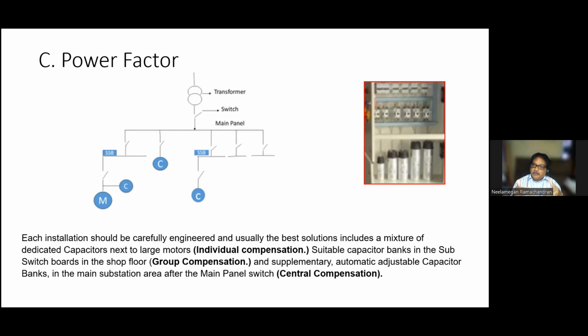At the motor incoming, we have to connect the capacitor. To my knowledge, all motors of 10 HP and more have to be connected with a capacitor, so that when the motor is switched on, the capacitor comes into the circuit. By dividing like this, we can easily maintain 0.96 and 0.94. Now, in certain states, they are charging EB in kVA, not in kWh.